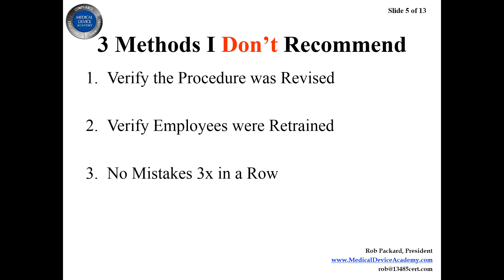Another method I see a lot, especially with contract manufacturers, is saying they'll check to make sure it doesn't happen in the next three orders. But if you only order something once every six months, you'll keep the CAPA open for 18 months before finding out whether it was effective — that's probably not a practical solution either.